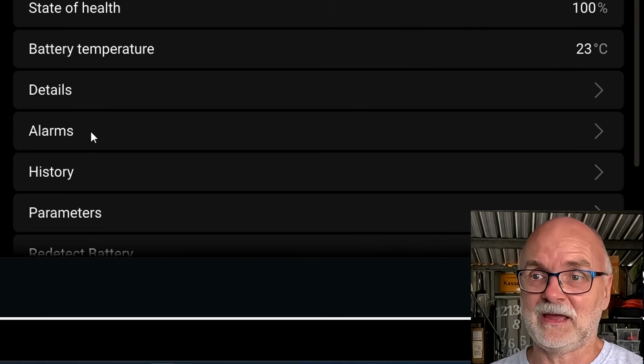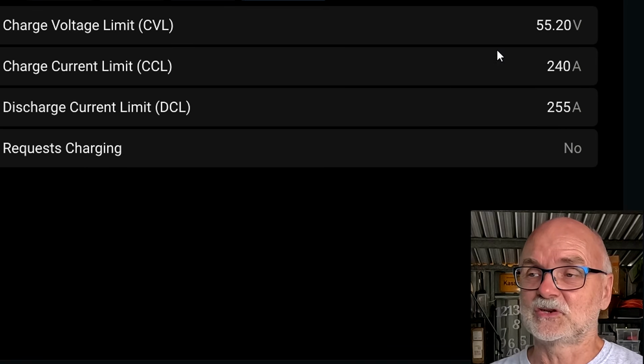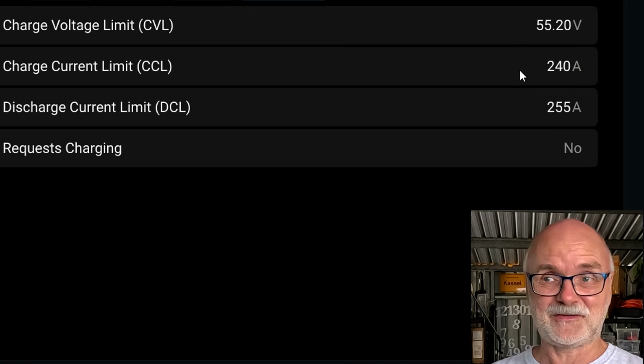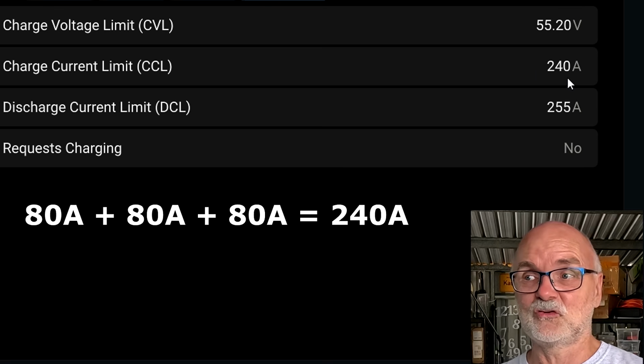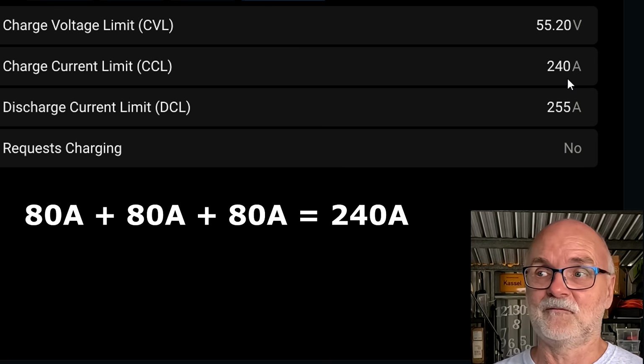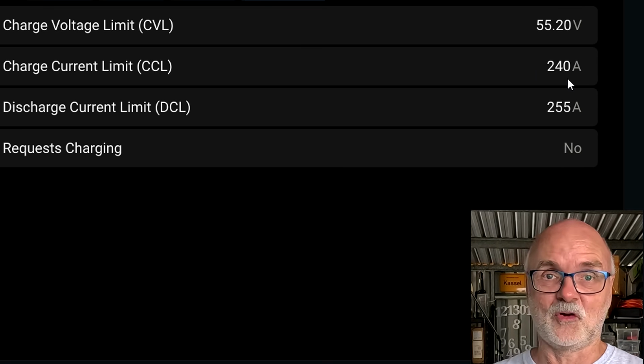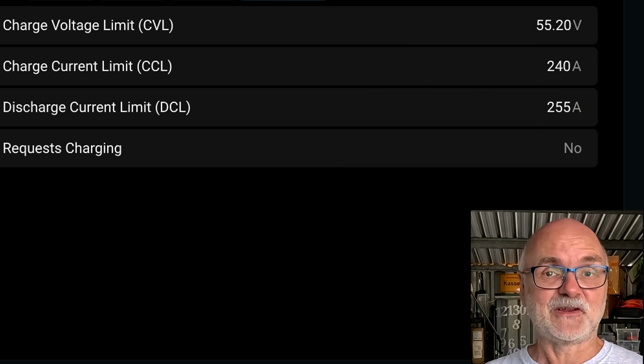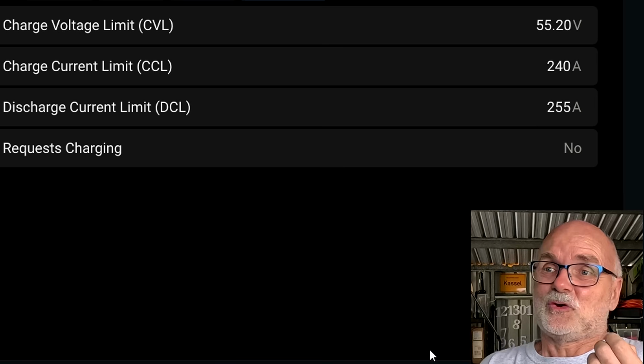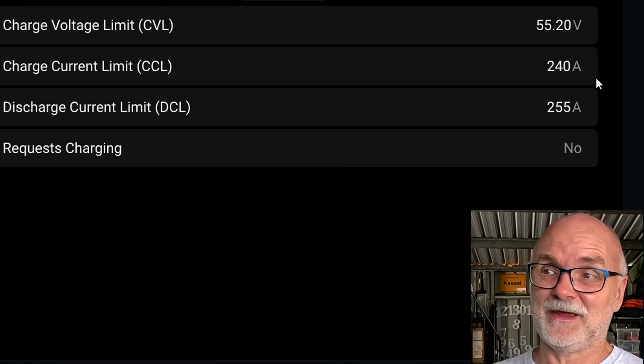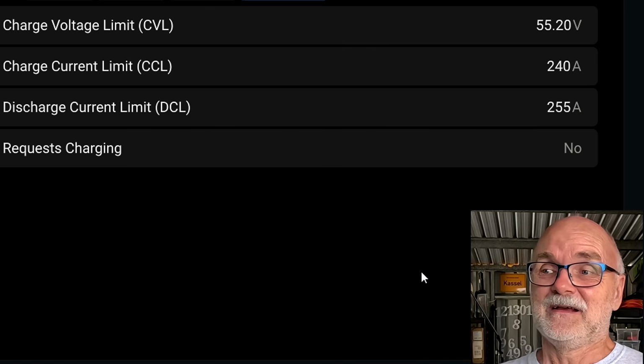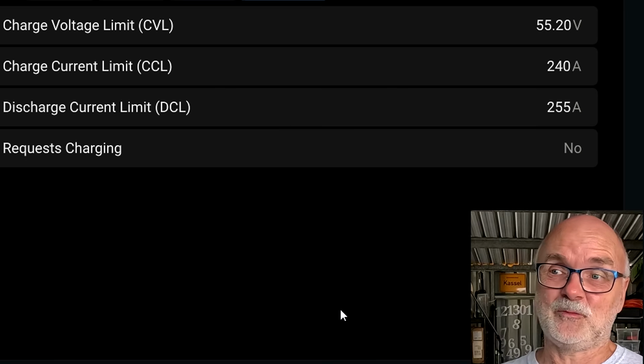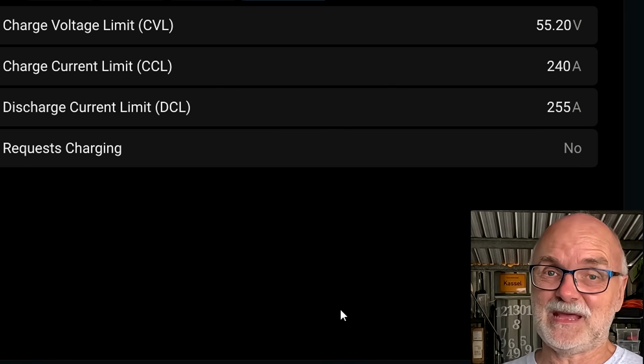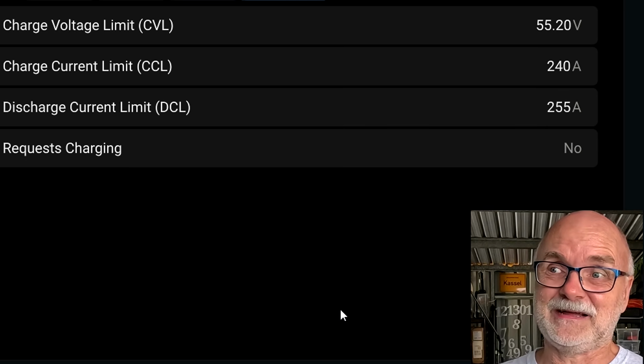And when we have a look at the parameters, it still charges to 55.2 volts, but it reduces the maximum charge current to 240, which will come from your inverter. So from 320 to 240, again, 80 amps are missing because one BMS is missing, but there's no alarm. So while what JK is doing here is kind of correct, we could also have the situation now that we have a stale BMS. The BMS is not unplugged from the rest, but it is not communicating anymore.